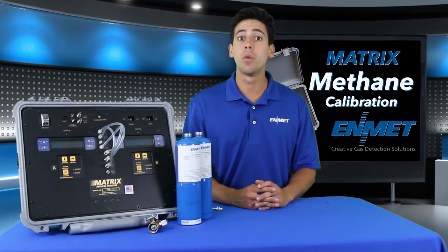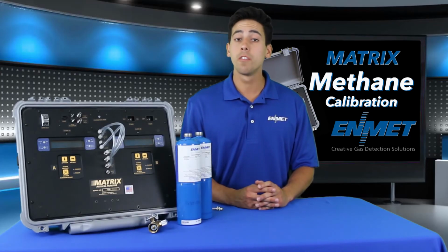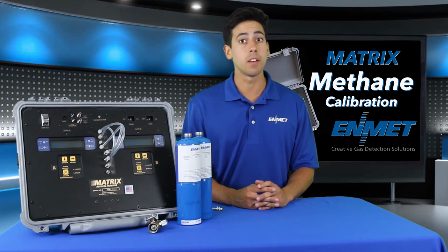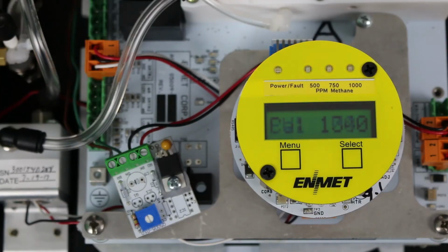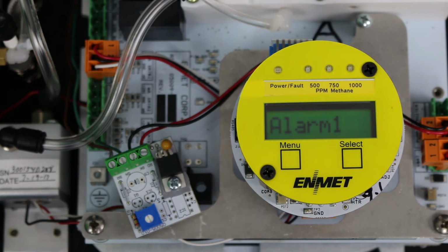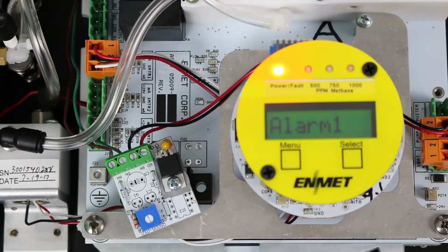The transmitter will monitor the sensor signal for stability for 2 minutes. If the sensor signal is stable after 2 minutes, the new span point will be accepted and cal OK will be displayed, indicating a successful span. You will be returned to the maintenance menu with the Alarm 1 option highlighted.